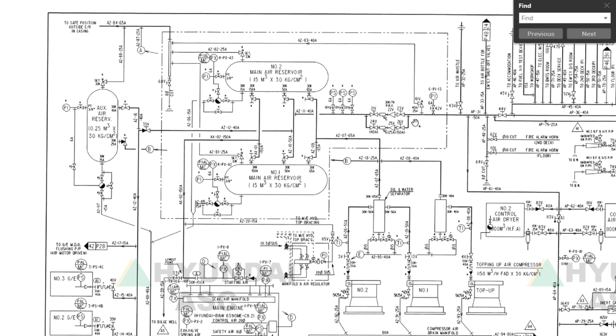Our pressure regulating valve is located here, and in most vessels and ships of this kind you will see it closely between these two air reservoirs — number one and two. Only one reservoir is under working condition and the other is on standby mode, pressurized, so you will have enough air in any emergency or during maneuvering when there is high consumption of compressed air. The line to the main engine goes direct at 30 bar from the air reservoir, travelling here to the main starting valve of the main engine.